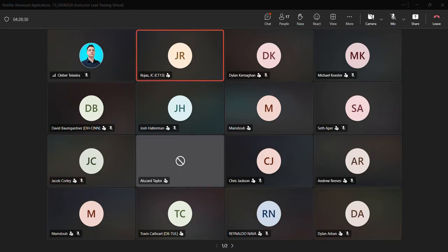Do you guys do the alerts as well? Do you alert the other floors that are not being evacuated, or you say nothing? Well, it's actually really special. The building's quite complicated. It has a jail side because you have people waiting for court, the bullpens. The fire alarm is sectioned, so it'll evacuate the civilian side of the building, but the jail side, the bunker room, they get an alarm, and there's a panel by the Sally Port area where they bring the prisoners in. There's a panel there that just locally annunciates to that guard. But other than that, the inmates don't hear anything. That's up to the staff to get them escorted where they need to go.